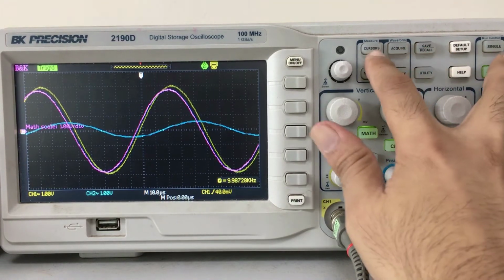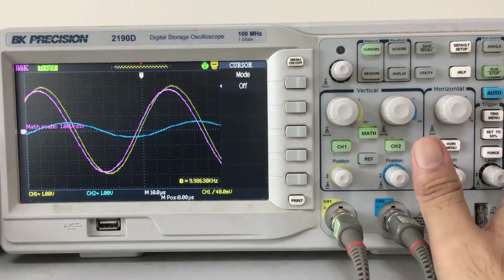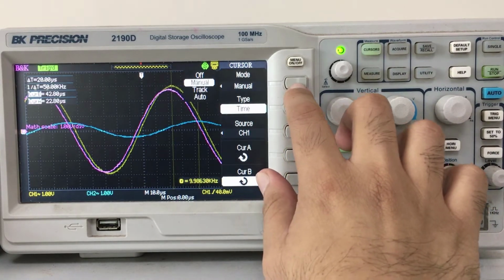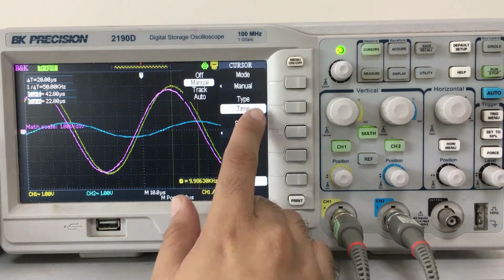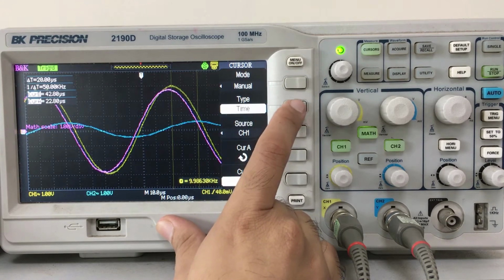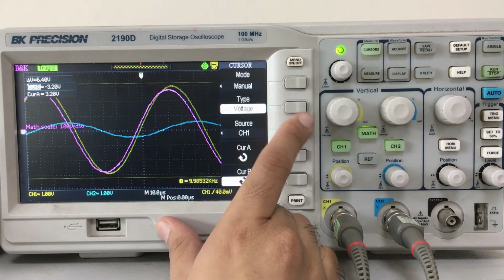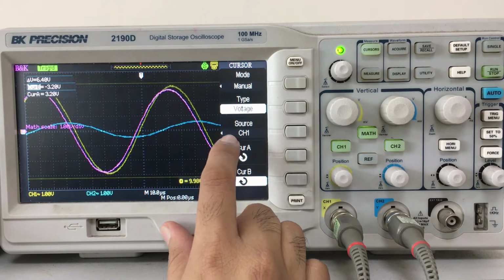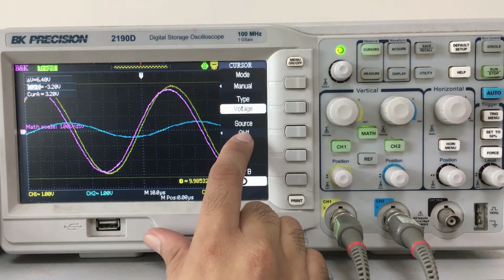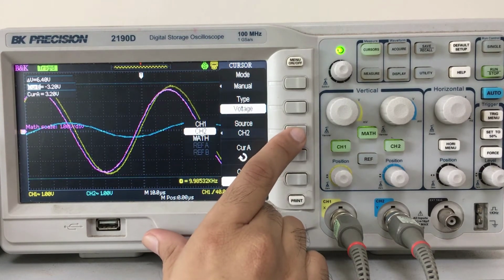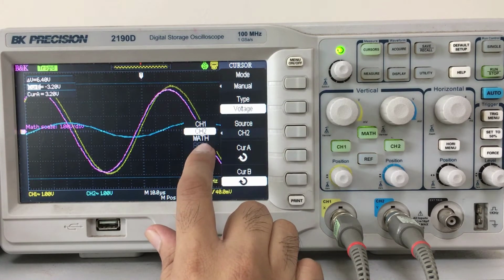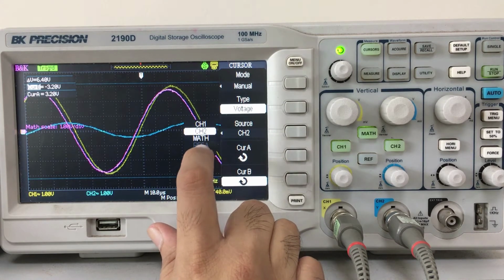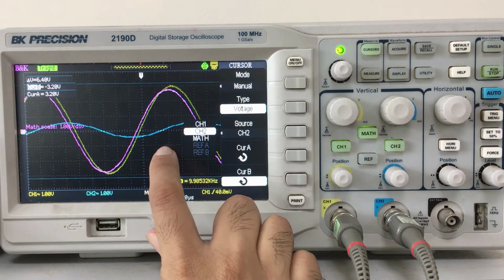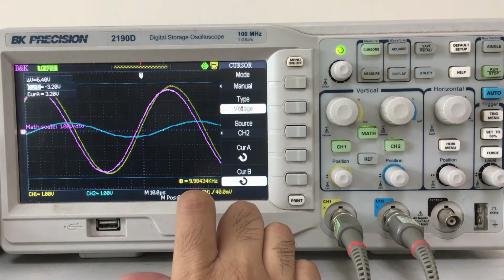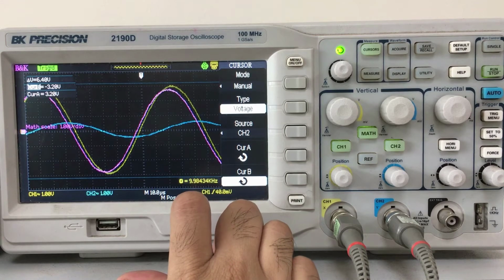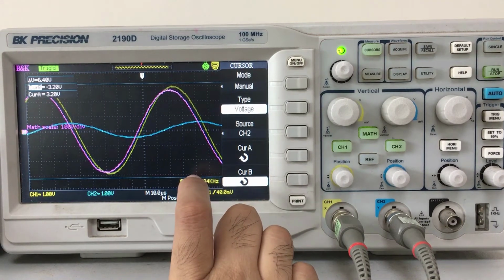We access the cursor by pressing the cursor button and turning the mode to manual, and this time we take the type as voltage since we are taking the voltage reading first. Now we have to choose the source. Pressing the source button shows three options highlighted: channel 1, channel 2, and math. These are the three signals displayed on screen, and you can choose any of them for the required readings.